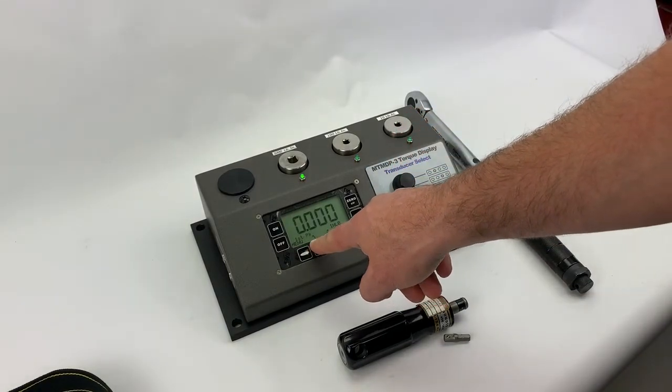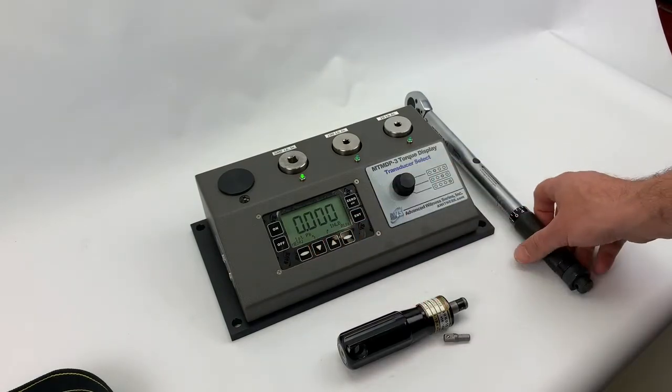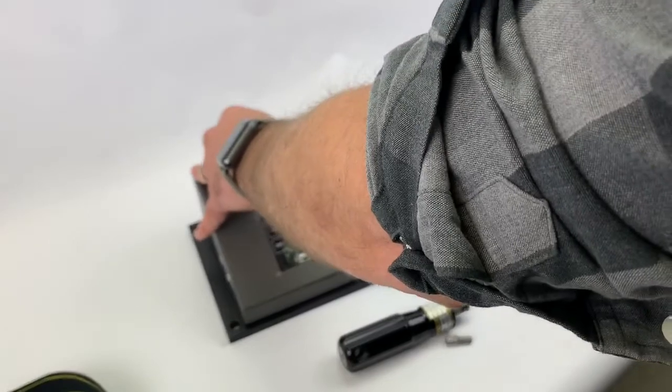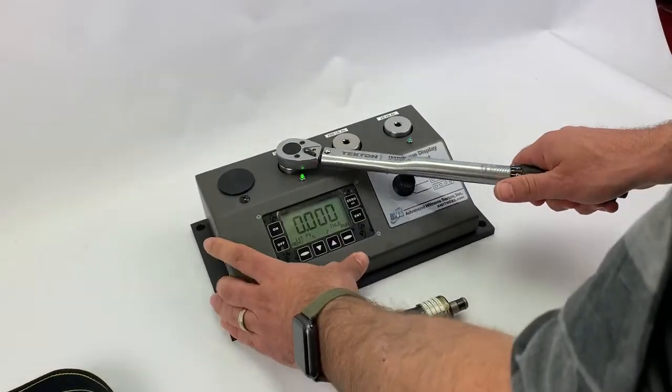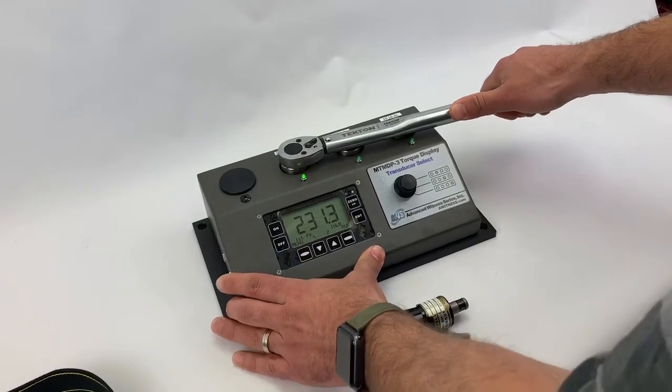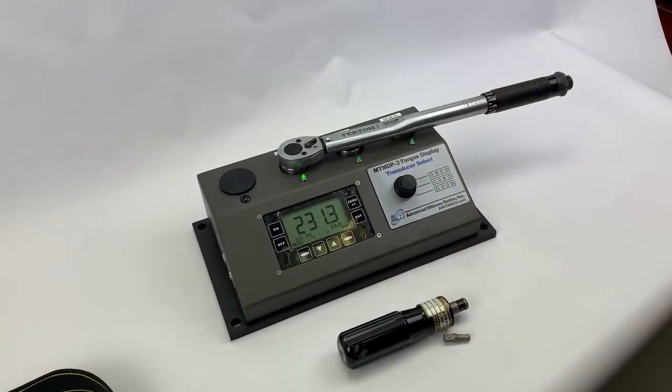I would change the mode to first peak, which is appropriate for click tools. I will put the wrench in and give it a pull until it clicks, and you'll see the torque.